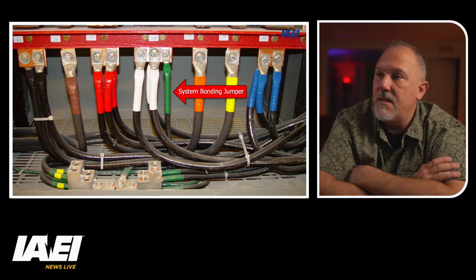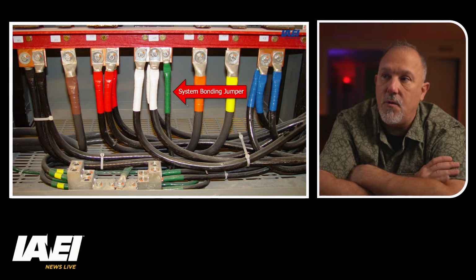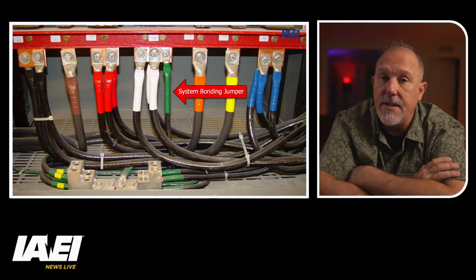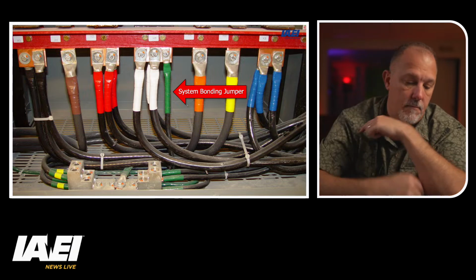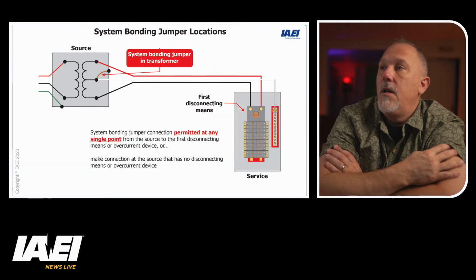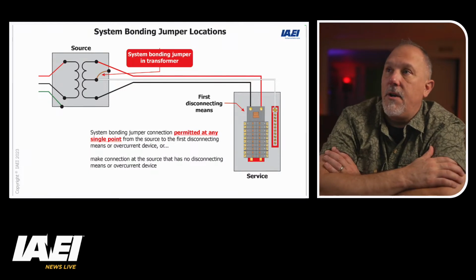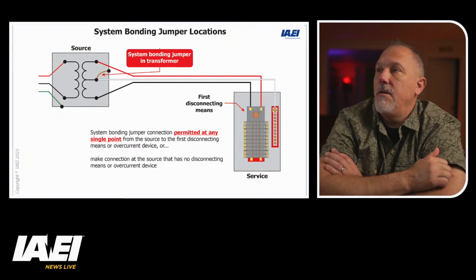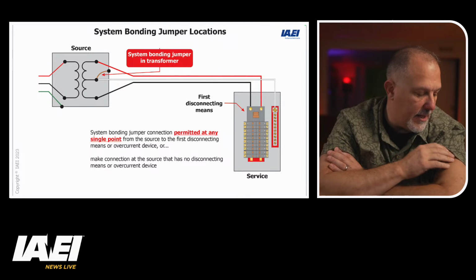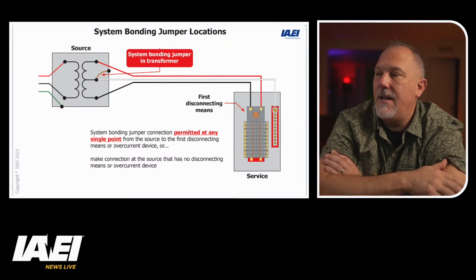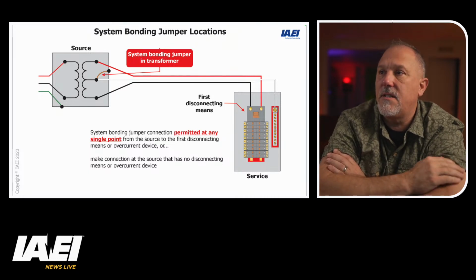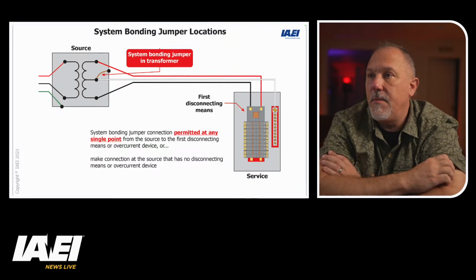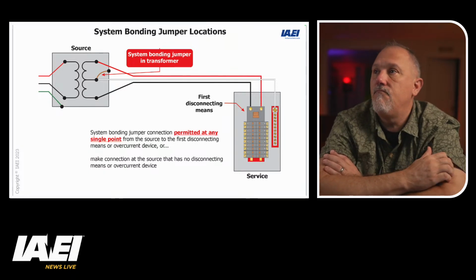But that system bonding jumper is making that connection in this transformer, and that's typically where you're going to find it. You're going to find this in the transformer itself. So there's your system bonding jumper in your transformer, and then there's your first disconnecting means there. And again, we put service. System bonding jumper connection permitted at any single point.